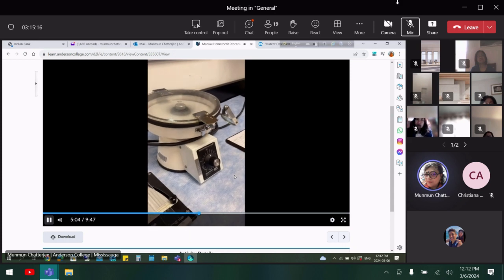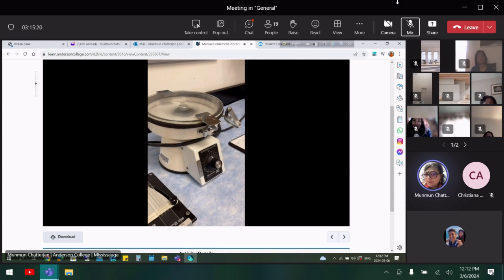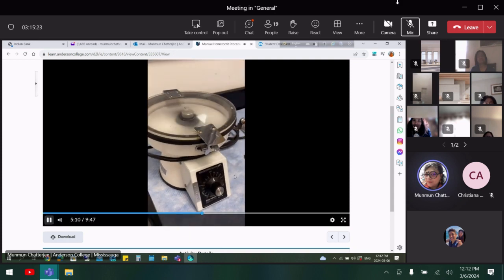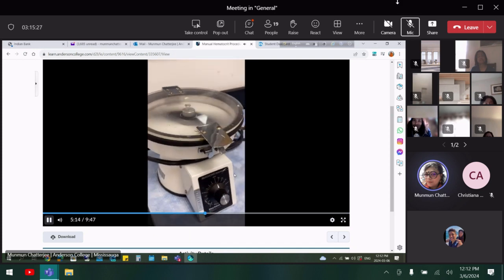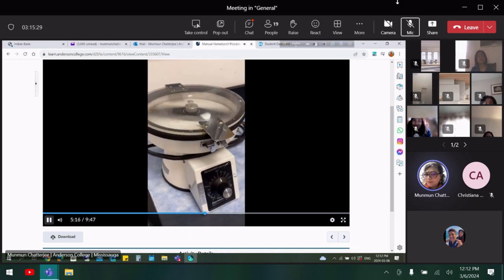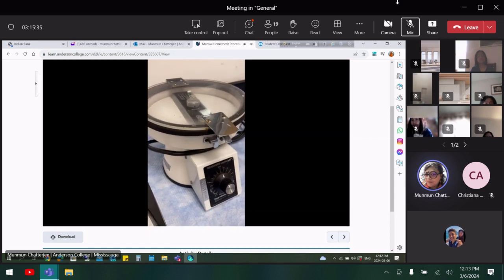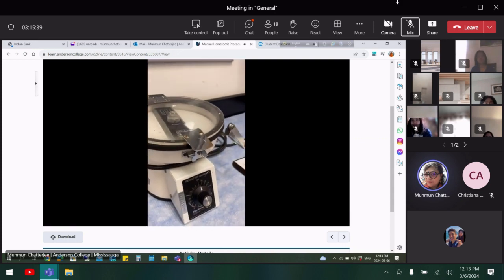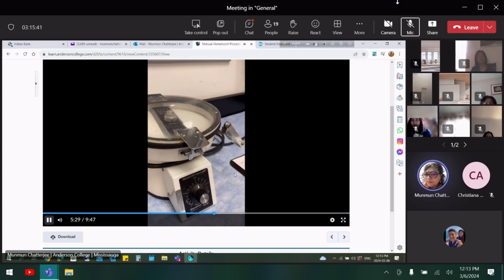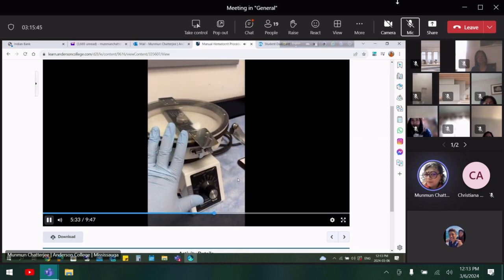So our centrifuge is just coming down right now, and we're going to wait for it to stop before we open it. There's no high-tech gadgets here that would stop us from opening it, but of course for safety purposes we would. Now, just like any centrifuge, we do have glass tubes rotating inside, and if one breaks, we would still follow that same procedure of let it sit for 30 minutes, have a sign warning anybody else from opening up this centrifuge for those 30 minutes, and we could take this to a biosafety cabinet and open it up there and properly disinfect it.